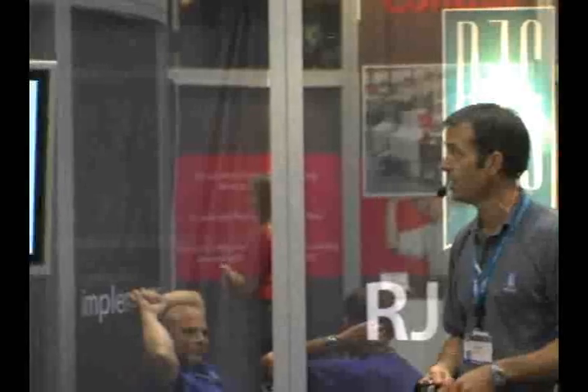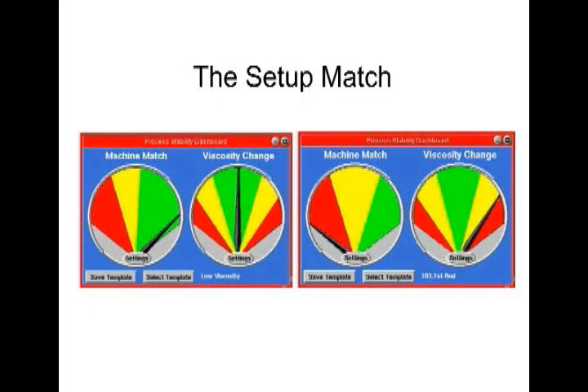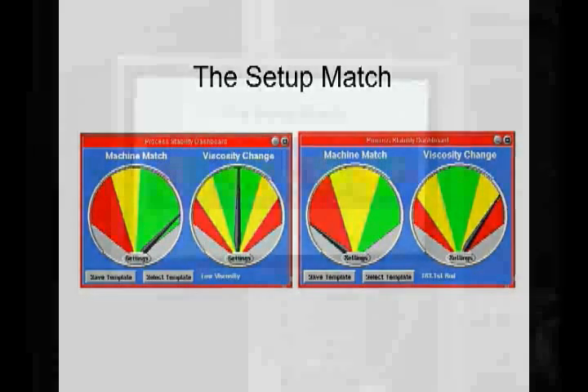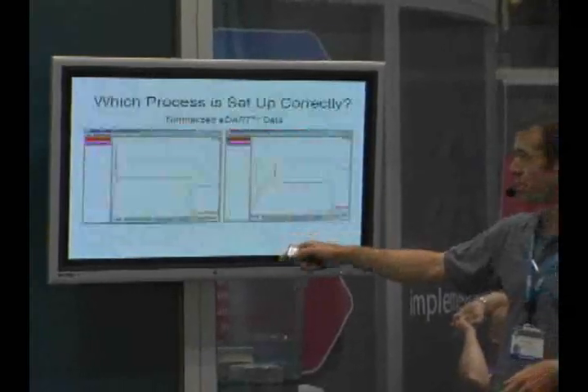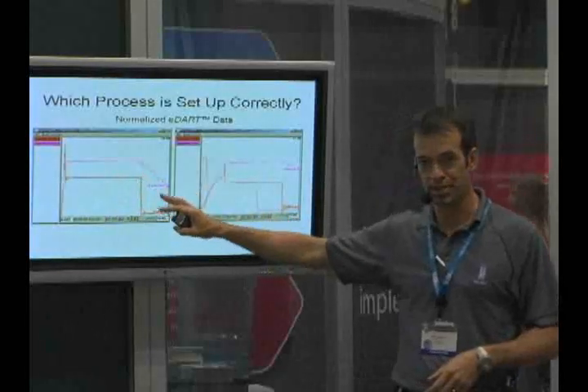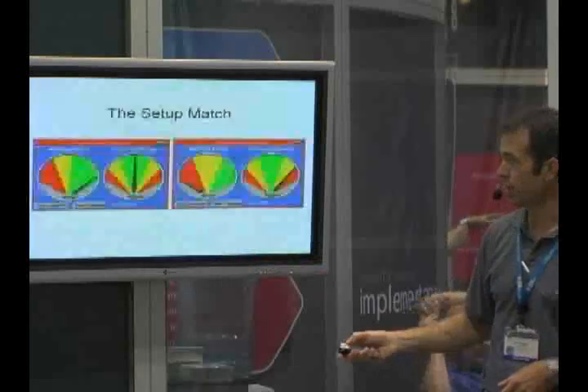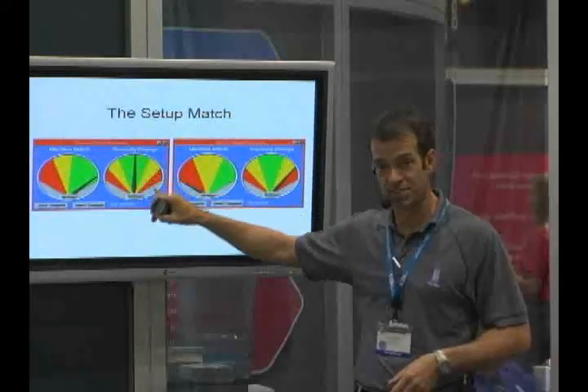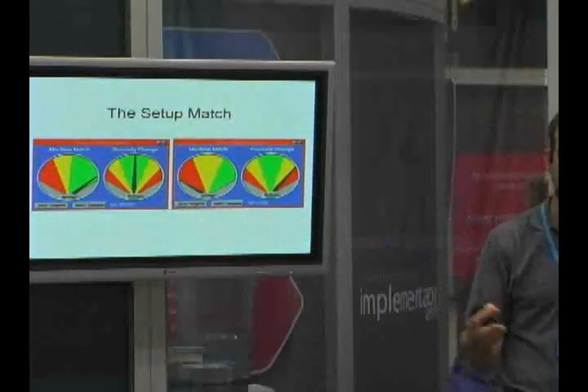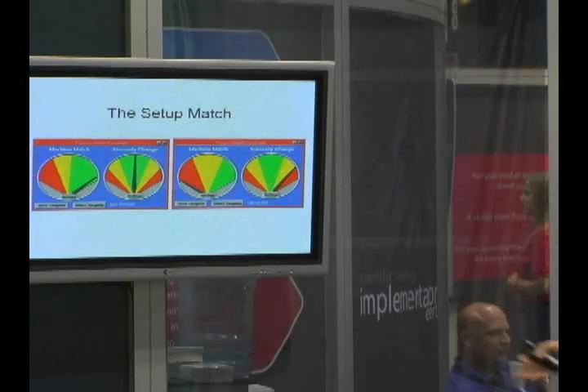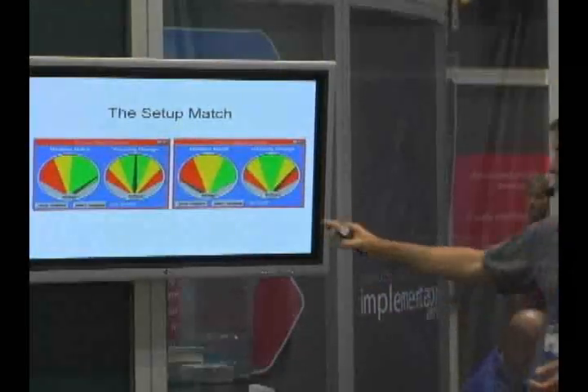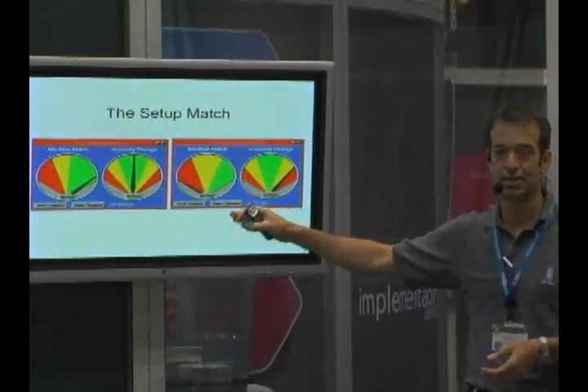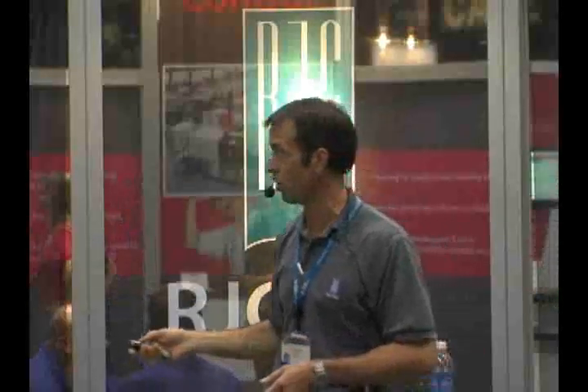So what we've done in our software is we've tried to turn the data into usable information. These graphs that are being displayed are looking at the reference template that's saved in the software and telling you, based on machine conditions and material viscosity conditions, if you have a match to the reference template. So without having to understand graph interpretation, you have an at-a-glance view of whether or not that process is matching the reference profiles. And as this screen shows, we have one match and one that doesn't match. These analog-type gauges have been able to identify that. Now, as a production manager, production supervisor, you can contact the appropriate people to say, there's an issue here, we need to figure out what went on.